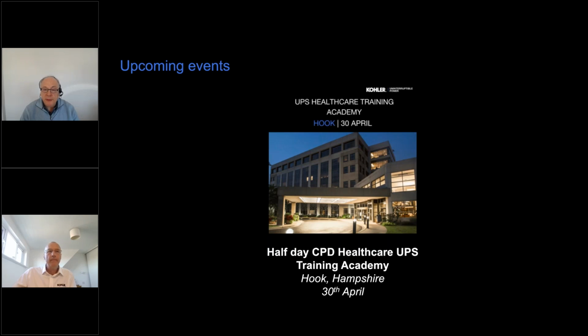Thank you. You've stressed the importance of maintenance and servicing. Somebody's asked, how often does a hospital UPS need servicing, and what's actually done? Okay. With any UPS, we have to follow the manufacturer's recommendations. HTM says at least once a year, but many manufacturers will say 2 times a year. And also there is maintenance to be done by the users themselves. So we want you to go in on a monthly check, make sure everything's working, make sure that the batteries will work if they're needed. But when we go in and do a maintenance, we are there to ensure that the UPS does as it says it's going to do, or warn you that it's not, and give the recommended actions to get it back up to standard. So we are going to operate the UPS, calibrate the UPS, test the UPS, and ensure that it's in absolute tip-top condition, and warn you if there are any problems coming up.